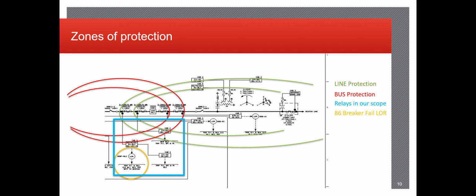On the opposite side of it, testing them can be quite dangerous, especially if you are testing something that runs to that lockout that also covers stuff that is in service equipment, meaning you could have an operation occur when doing your testing on the new equipment and accidentally open up a breaker that is in service, causing an outage and making the client very unhappy.